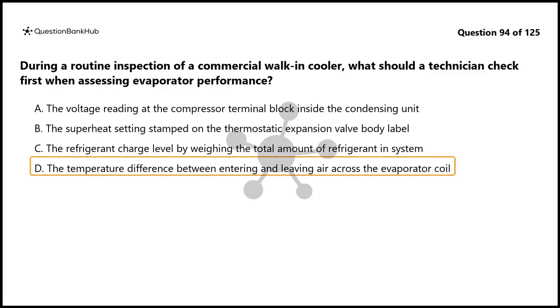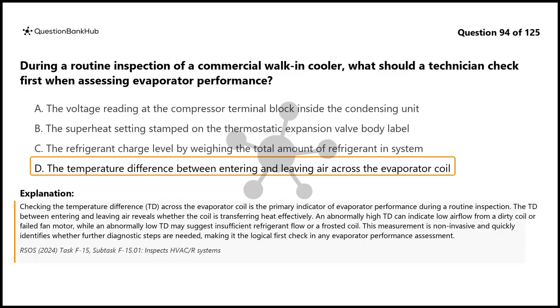The correct answer is D. Checking the temperature difference, TD, across the evaporator coil is the primary indicator of evaporator performance during a routine inspection. The TD between entering and leaving air reveals whether the coil is transferring heat effectively. An abnormally high TD can indicate low airflow from a dirty coil or failed fan motor, while an abnormally low TD may suggest insufficient refrigerant flow or a frosted coil. This measurement is non-invasive and quickly identifies whether further diagnostic steps are needed, making it the logical first check in any evaporator performance assessment.